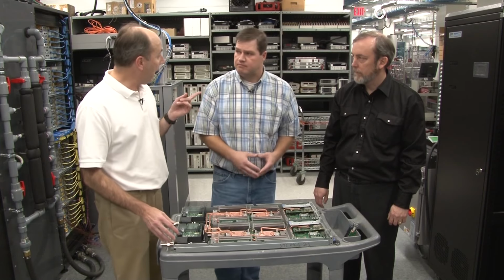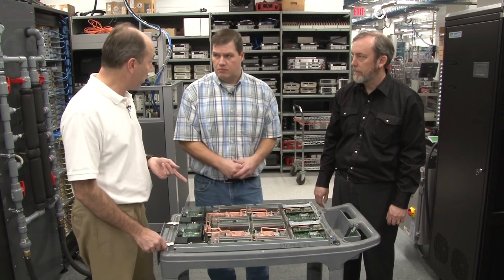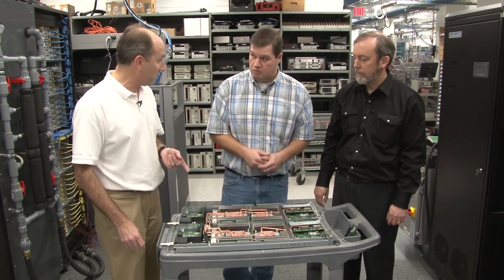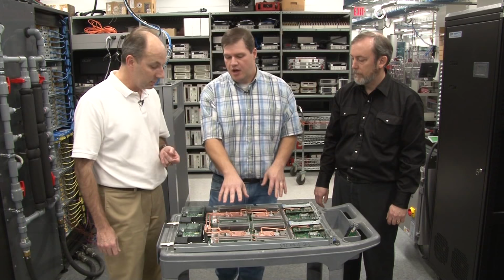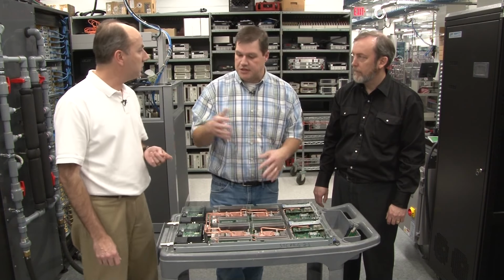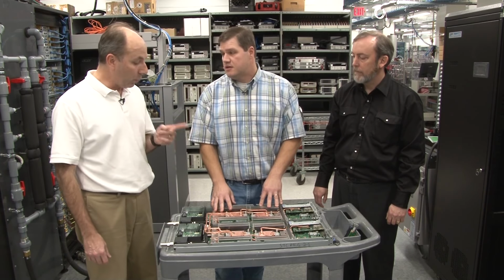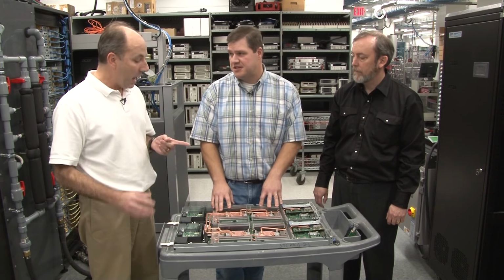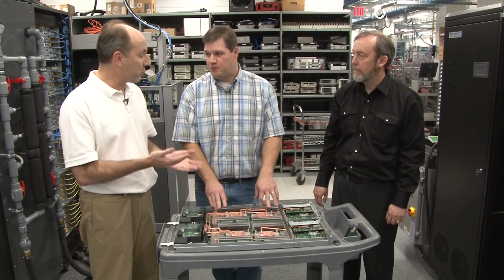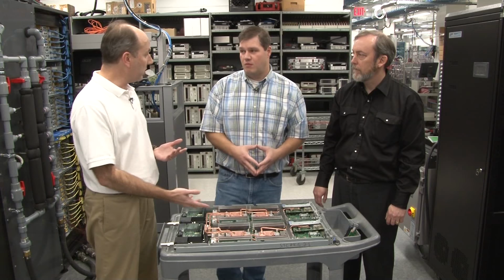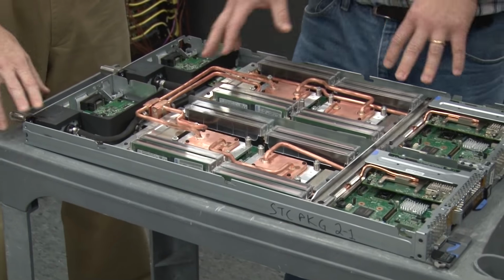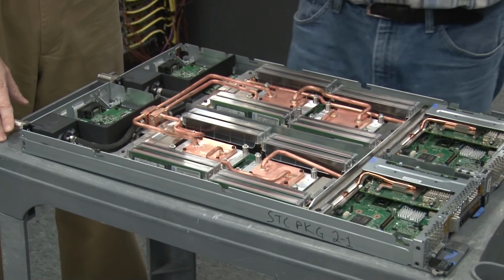And actually I would add too, this water can be warm water, right? This does not have to be chilled water. That's correct, the only limitation we have for that water is we go from 18 to 45 degrees Celsius, and there's still enough temperature differential to cool these components. So there's no restriction in terms of that water usage.